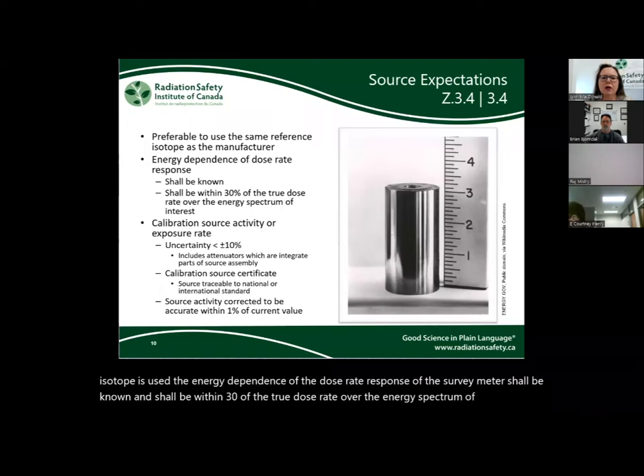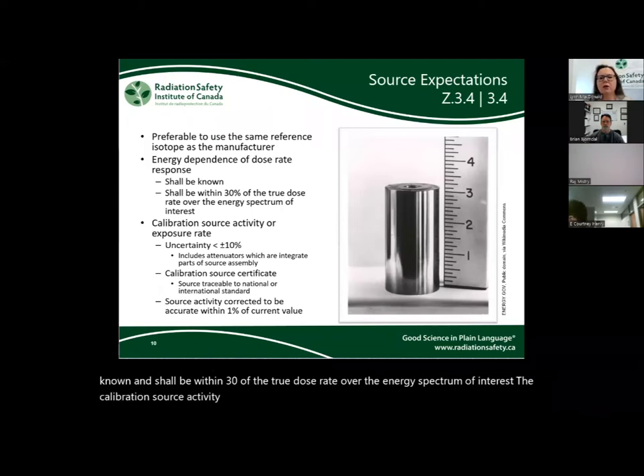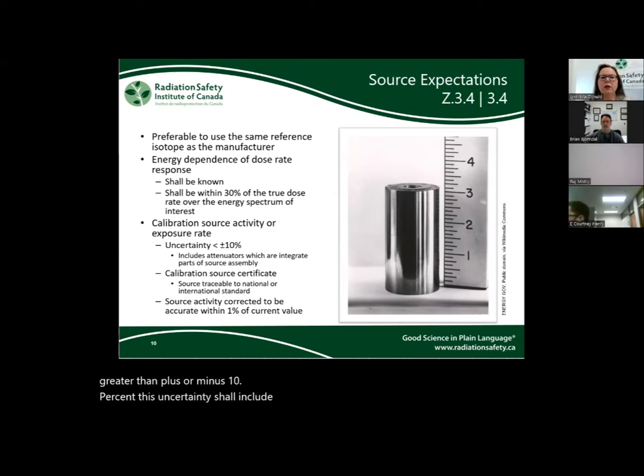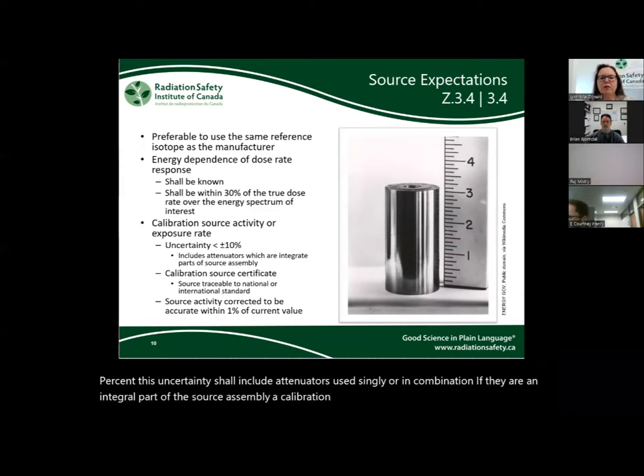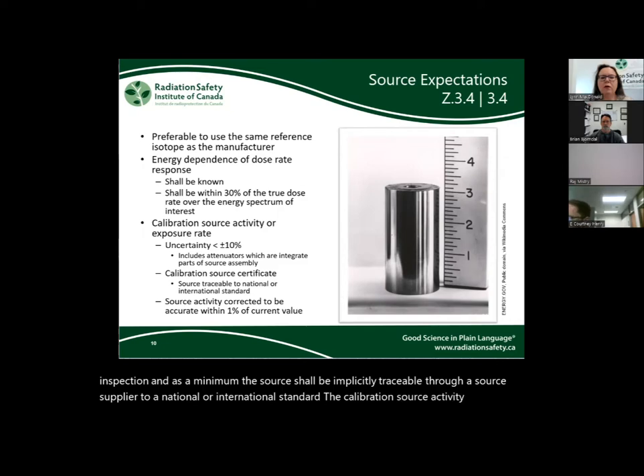The calibration source activity or exposure rate shall be known to an uncertainty of not greater than plus or minus 10%. This uncertainty shall include attenuators, used singly or in combination, if they are an integral part of the source assembly. A calibration source certificate shall be available for inspection, and as a minimum, the source shall be implicitly traceable through a source supplier to a national or international standard. The calibration source activity shall be corrected for decay at a frequency to ensure its activity is within 1% of its current value.